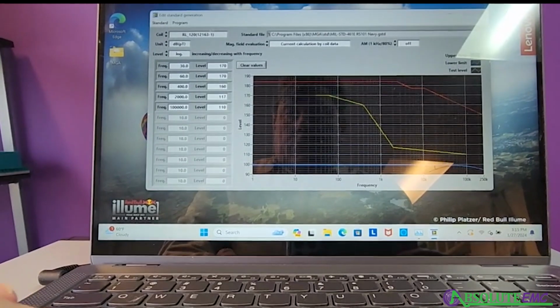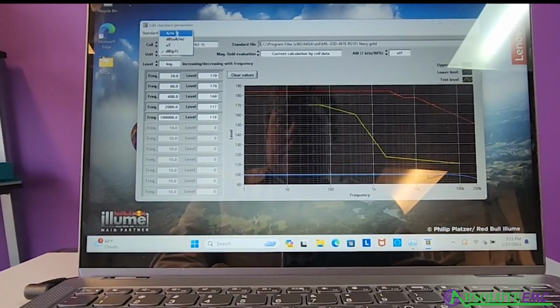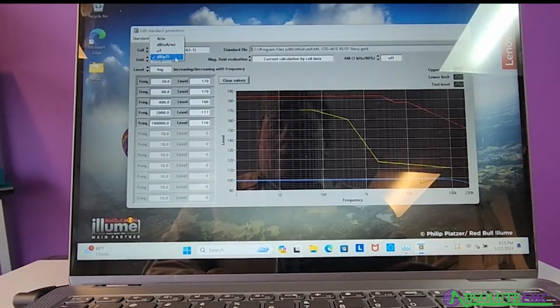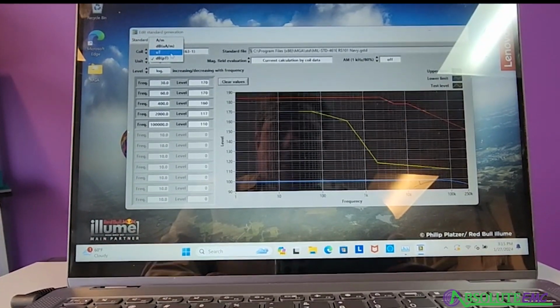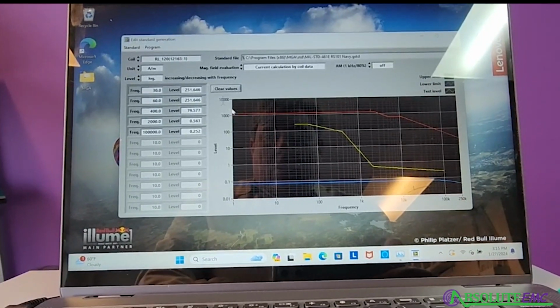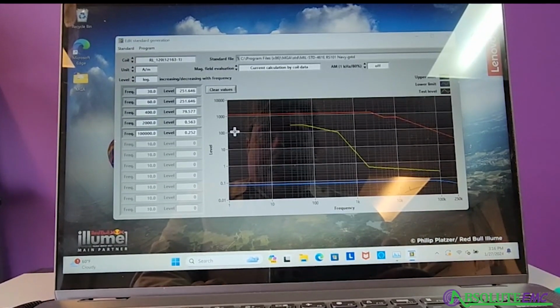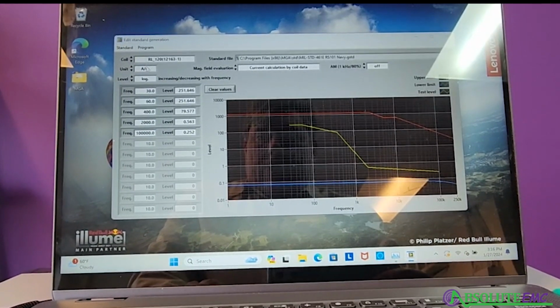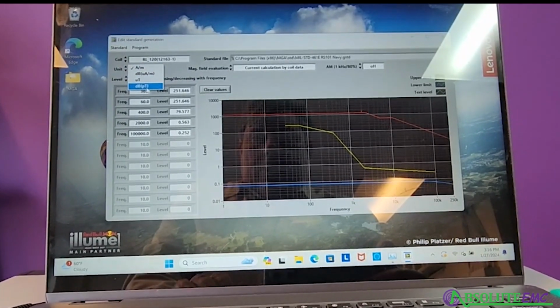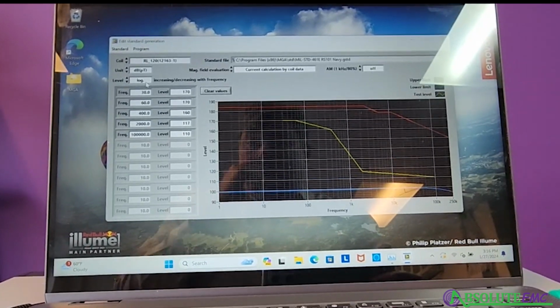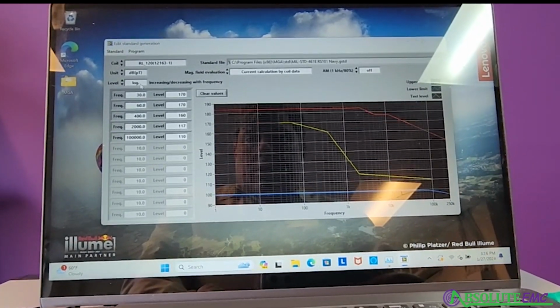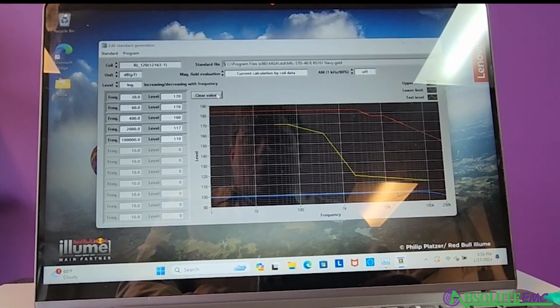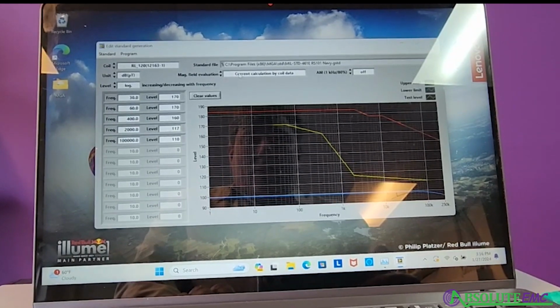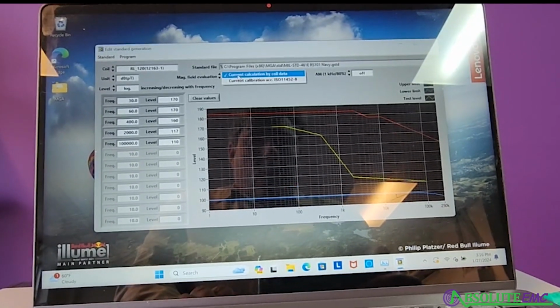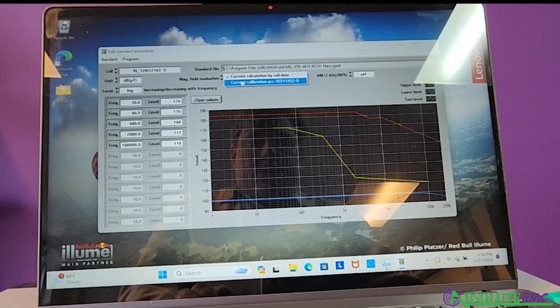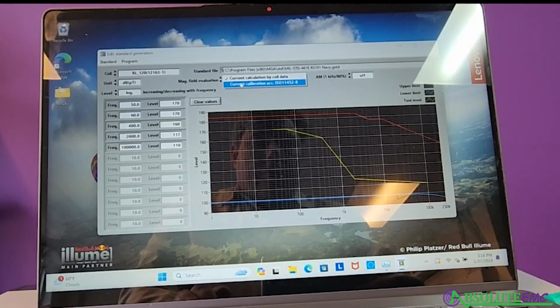So we have the ability to change units from dB picoteslas, amps per meter, dB microamps per meter, or microteslas. If we do that change, so we go to amps per meter, everything changes to amps per meter in the graph and over the left. So it automatically changes all the units. Let's go back to what the standard requires. You also can change your frequency steps, whether it's log or linear. You have the choice between current calibration by coil data or current calibration according to ISO 11452-8.